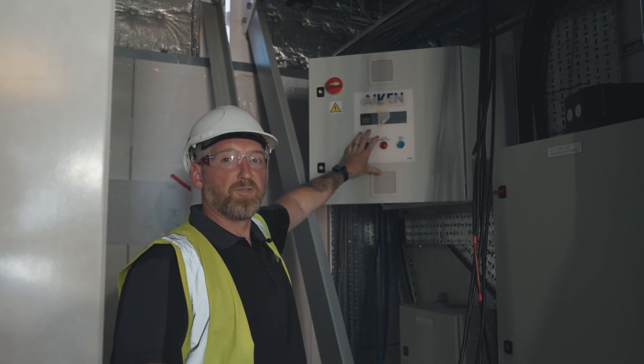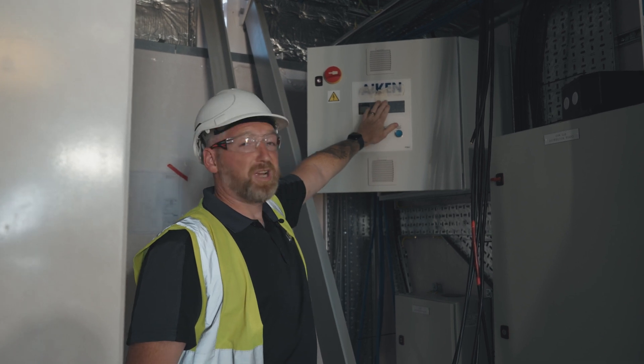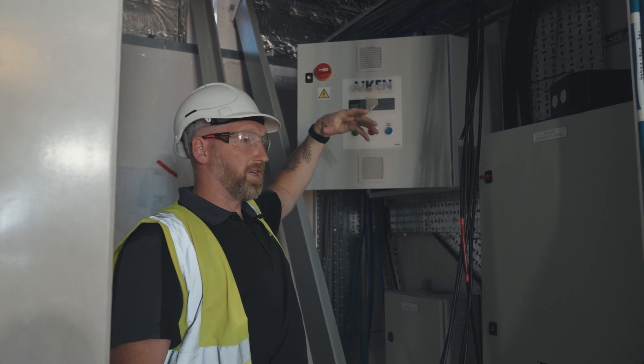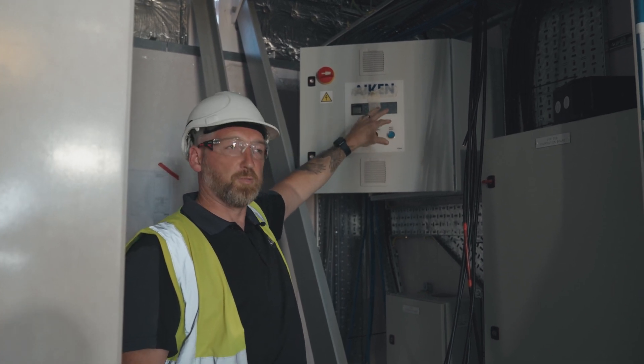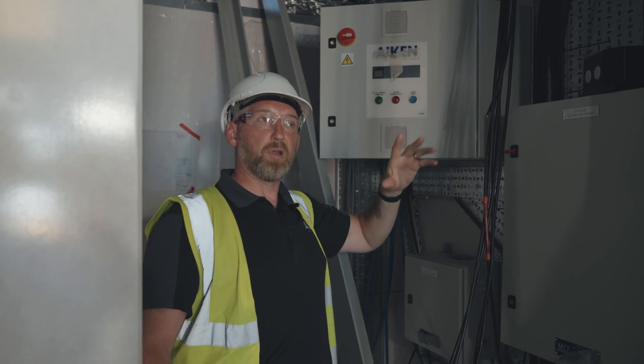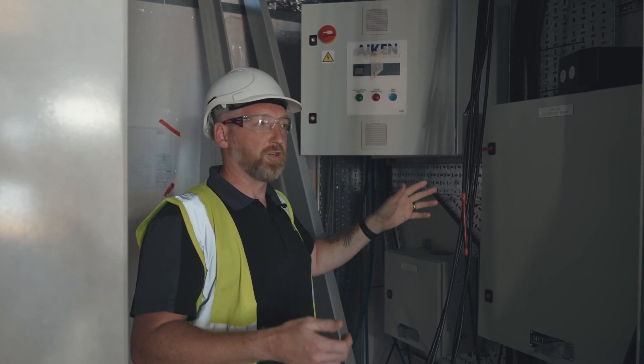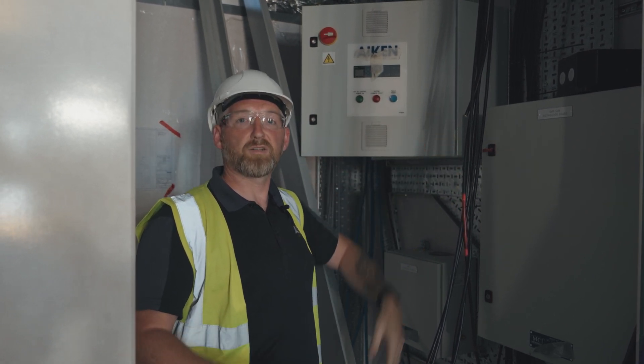This will be the main control panel for the HVAC system for this gym area, with a PLC-based controller which is pre-programmed at the manufacturer. When we do the factory acceptance test, we will run through all the settings of the programs and pre-set everything. So when it goes offshore, it will basically be plug and play - power supplies are hooked up, switch it on, and it will be pre-set ready to start working as required for the offshore module.